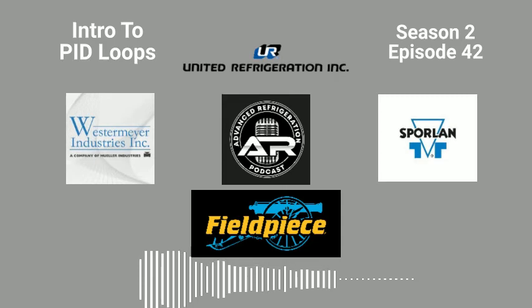By the time the input updates, that's 1 to 2 seconds. By the time the control updates, there's another 2 seconds. And then by the time the PID is added to the output, there's 20 seconds. So now 24 seconds have gone by. If you don't have something that's reacting super fast, that's okay. But if you're trying to control a valve, say a CDS valve doing a defrost differential valve, 24 seconds is going to kill you. You're going to overshoot or undershoot big time. So that's why you need to make sure that PID loop is updating as fast as it possibly can.